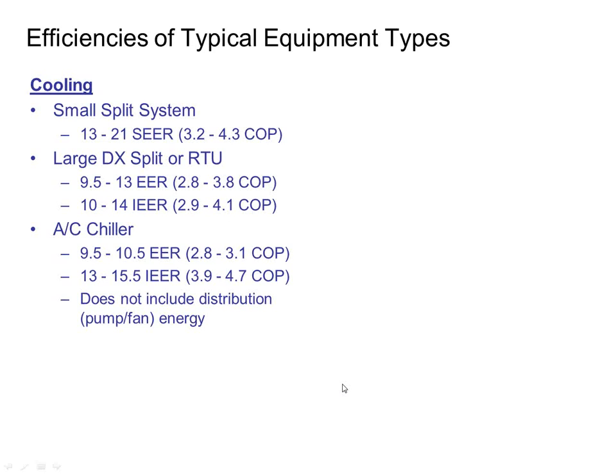Air-cooled chillers are also rated in EER. You can't compare it directly to rooftops and DX splits because those units have the air distribution mechanism included, which is a fan. The chiller does not have the distribution mechanism included, which is a pump. So it's not a fair comparison, but just if we had to do it, I've thrown up on the screen there's kind of your range.